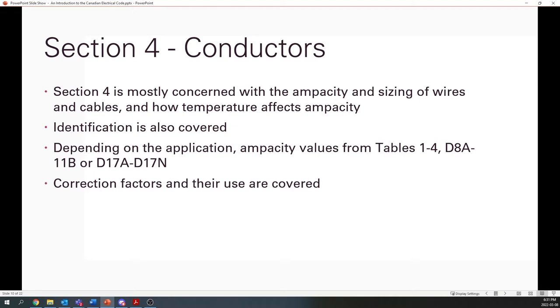So section four is on conductors. Section four has to do mainly with the ampacity and sizing of wires and cables and how the temperature affects the ampacity. As we all know, the resistance of wire goes up when the temperature increases. So that is going to affect the current rating of the cable, how much current the wire can handle. And of course, because we don't have superconductors, the more current you have down a wire, the resistance is going to generate heat. The heat is going to heat up the wire. The resistance is going to increase from the increased heat. And it's this kind of positive feedback loop until it reaches some new equilibrium point.